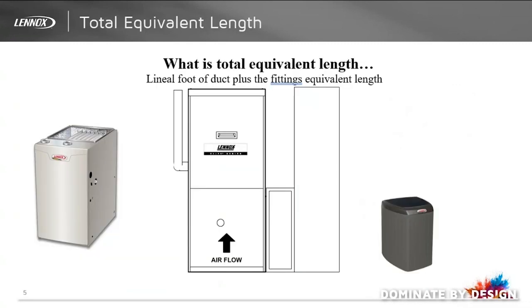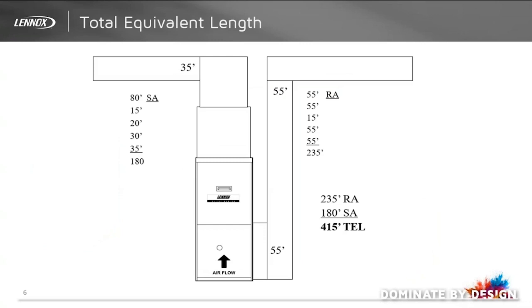So what does total equivalent length mean? Equivalent length is the lineal foot of duct work plus the equivalent length of the fittings. Now that we know what total equivalent feet means, it's time to start calculating all of the duct work — both supply ducts as well as return air ducts — for the total equivalent length. This is where the 415 feet comes from, and it is here where most dealers get lost or simply choose not to calculate duct work they can't see, especially in existing homes or retrofit applications as opposed to new construction from a blueprint. For these reasons, duct work systems get overlooked.